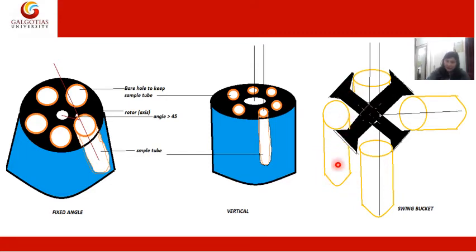This is the position of the sample tube when we are not running our process, but during a spin, this sample tube turns to 90 degrees so that the centrifuge gives more centrifugal force, because we know that the RPM also depends on the R, and here you can see that R is increased when the sample tube turns to a 90 degree angle and the separation happens in this direction. So these are the pictures of different types of rotors for clear explanation.